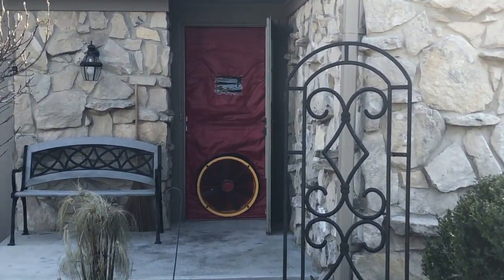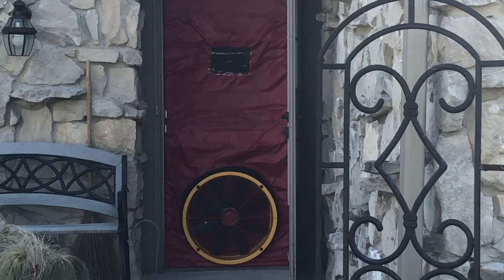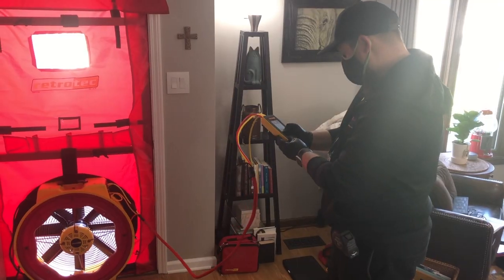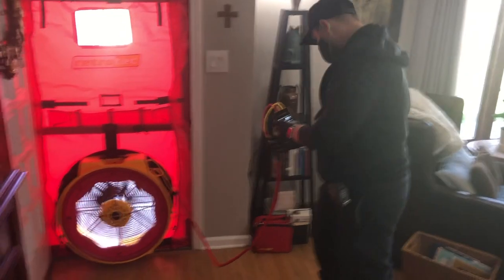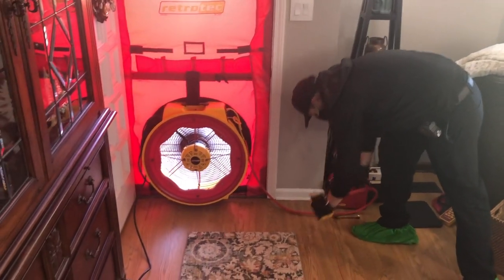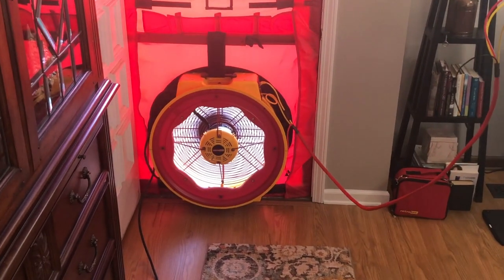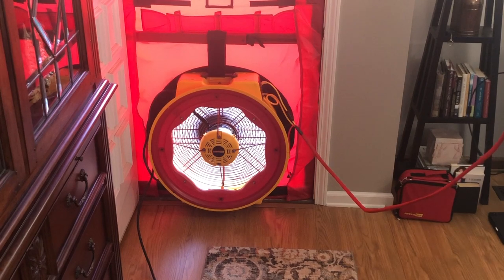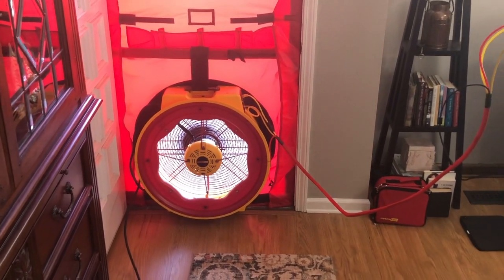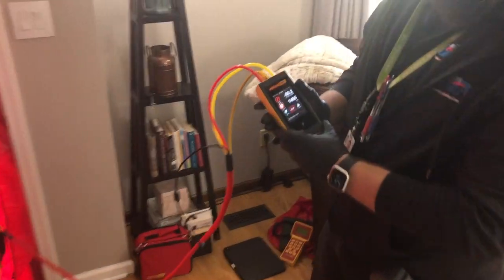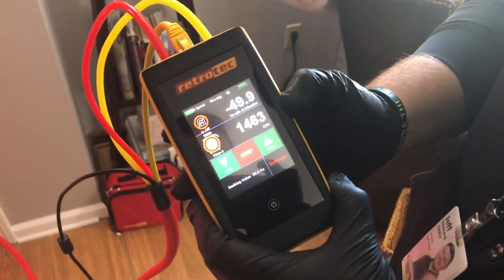Jeff came out and performed a blower door test. This fan is set up in the doorway and blows air from inside out, pulling the home into a negative pressure. With the house in a negative pressure, leaks in the home's envelope where air and humidity can infiltrate become evident. Once we achieve our 50 pascals, what we can actually look at here is a couple.